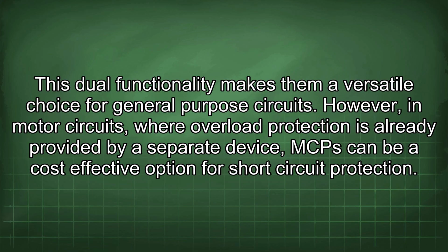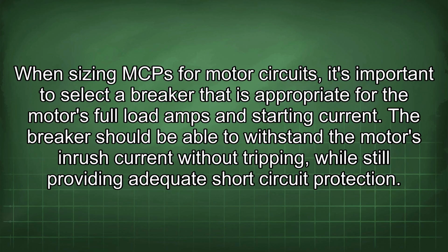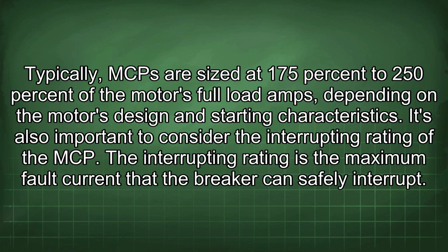for short-circuit protection. When sizing MCP for motor circuits, it's important to select a breaker that is appropriate for the motor's full load amps and starting current. The breaker should be able to withstand the motor's inrush current without tripping, while still providing adequate short-circuit protection. Typically, MCP are sized at 175% to 250% of the motor's full load amps, depending on the motor's design and starting characteristics.